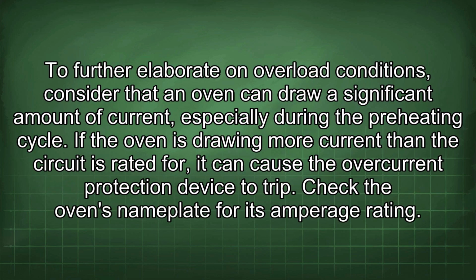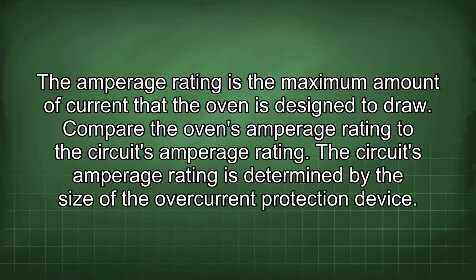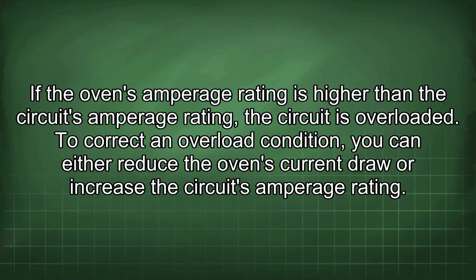To further elaborate on overload conditions, consider that an oven can draw a significant amount of current, especially during the preheating cycle. If the oven is drawing more current than the circuit is rated for, it can cause the overcurrent protection device to trip. Check the oven's nameplate for its amperage rating. The amperage rating is the maximum amount of current that the oven is designed to draw. Compare the oven's amperage rating to the circuit's amperage rating. The circuit's amperage rating is determined by the size of the overcurrent protection device. If the oven's amperage rating is higher than the circuit's amperage rating, the circuit is overloaded.